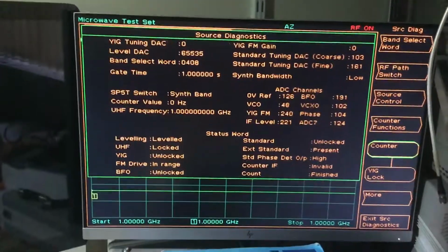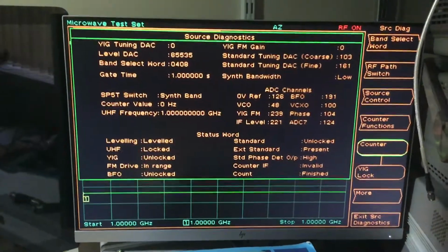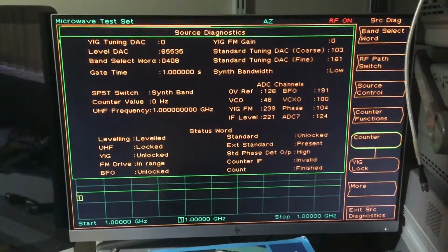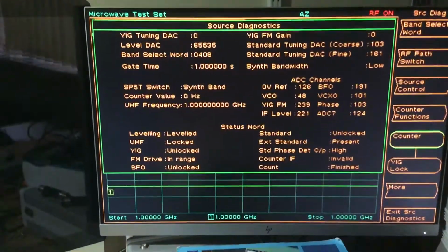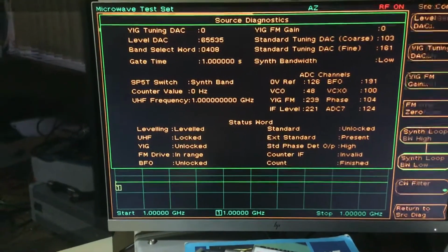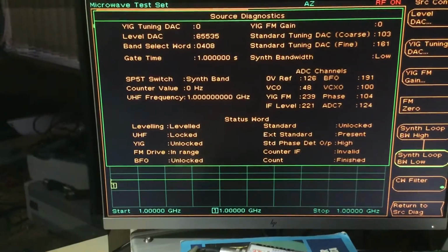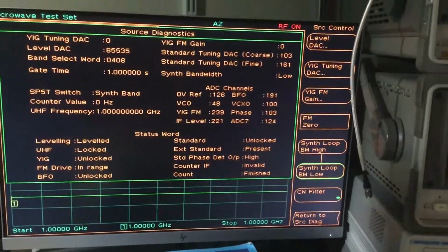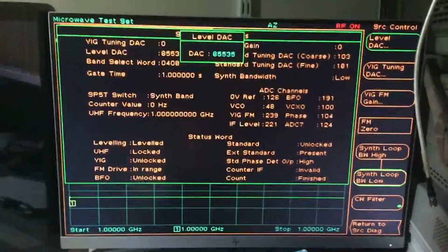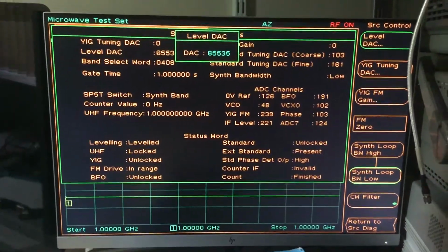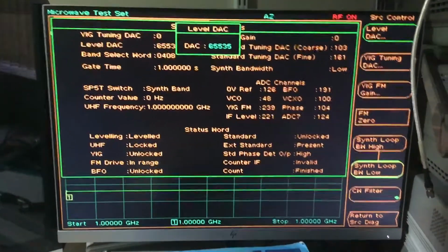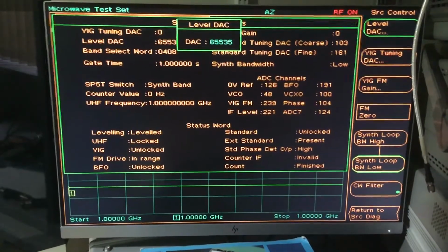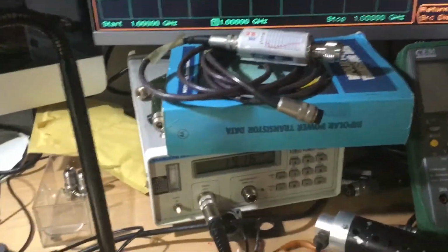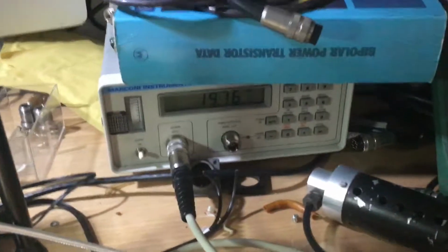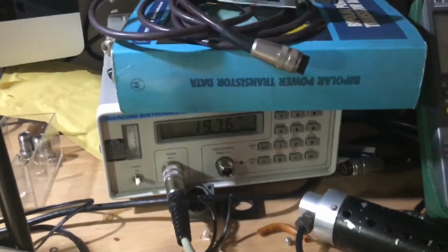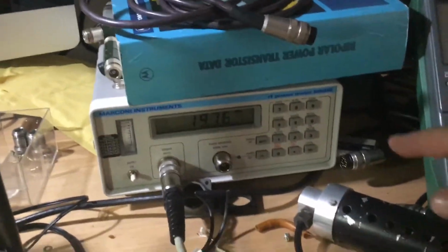Now in this particular case we're in the service menu, a hidden menu within the test set that gives us access to the diagnostics functions. If I do source control, and I think it's, let's have a look here, there's level DAC, so we'll select that. We've got the value that it currently is, and we can adjust that just to see what happens with the output, because this is a diagnostics menu, not a calibration menu. So what I've done is connect the microwave sensor to the Marconi power sensor thing here, this gadget.